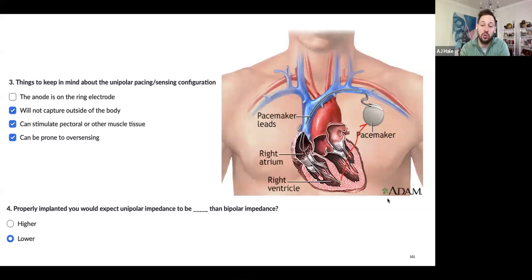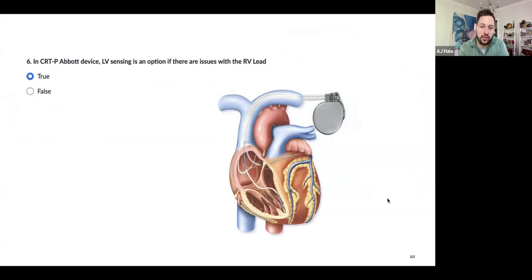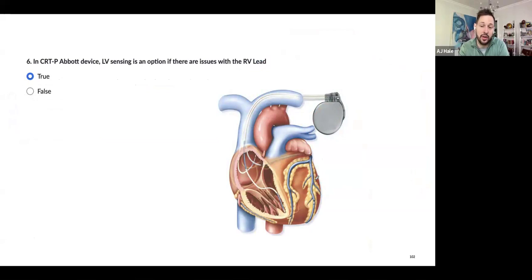For Abbott devices, you do have LV sensing as an option for an LV pacemaker, but not for Abbott ICDs. If you're having trouble with your RV lead, you can still use your LV vector. Remember that stability is generally not as good in LV leads, especially newly implanted ones. If you just added an LV lead and change that to the sensing vector for a dependent patient and it drops into the atrium, it's going to sense atrial activity and withhold pacing when you may actually need it. I tend not to use it, and when I do it's when I'm very sure the LV lead is stable.